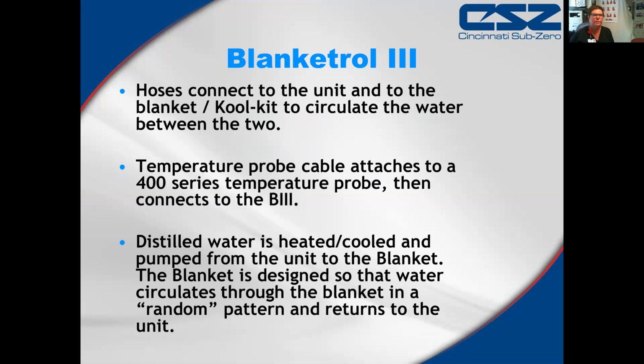In order for the machine to work to its full potential, you need a temperature probe attached to your patient, and that will depend on what your hospital has decided for a temperature assessment. Rectal is the least reliable. You could have an esophageal probe, which we use occasionally. We do like to use the probe that is connected to our Foley catheter. So we have special order Foley catheters that will sense the patient's temperature. And then if you had a patient with a pulmonary artery catheter, that is probably the most sensitive core temperature.